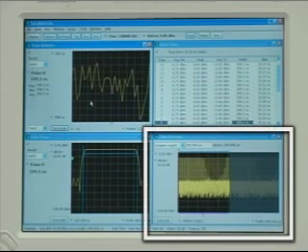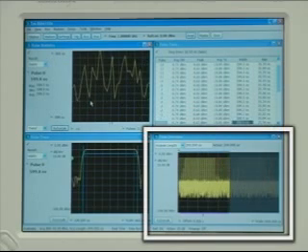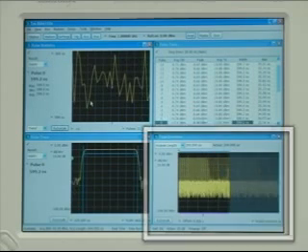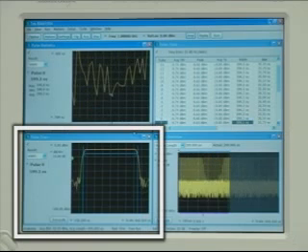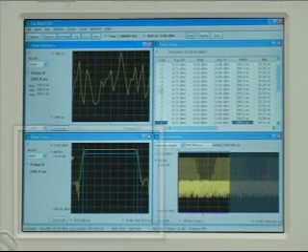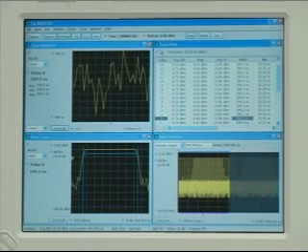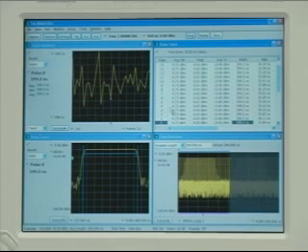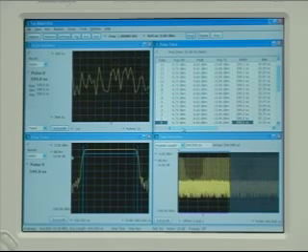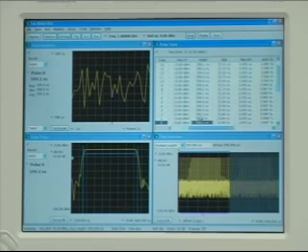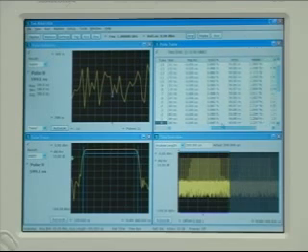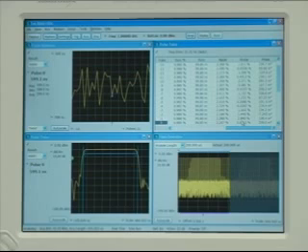The lower right display shows a time domain overview of the captured signal, and the lower left display shows the pulse view, which looks at an individual pulse from the captured signal. With pulse view, you can easily analyze many common parameters like the average on power, peak power, rise/fall times, and pulse-to-pulse carrier phase.